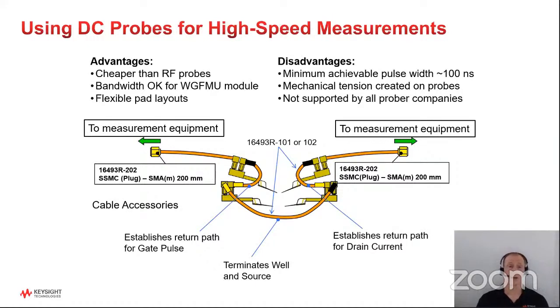If you're using DC probes instead of RF probes, which I think most people probably are because the cost of RF probes is pretty high, it doesn't mean you can't make pulsed or high-speed measurements. You can still do it, but you do need to have the proper setup or cabling. Here I'm showing a cable set that we make and you can purchase, which allows you to connect your probes together as shown here so that all of the correct return paths for the current are taken care of, and you don't get strange reflections and things like that. I'll explain what the WGFMU module is in a little bit, but it's probably okay to use for that type of measurement, maybe at 100 nanoseconds or a slightly faster pulse width as well. And it does give you the ability to have more flexible pad layouts.